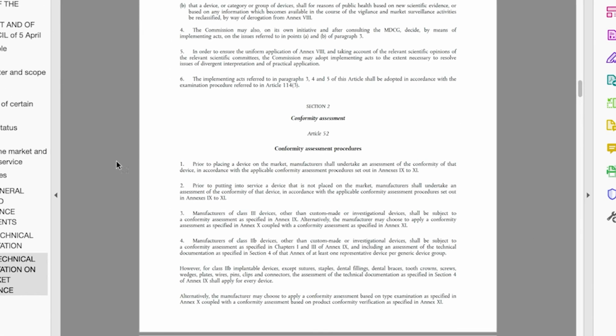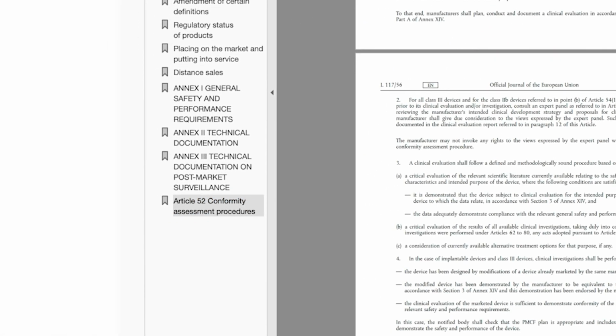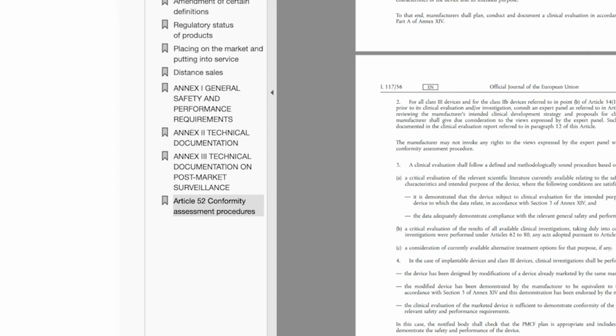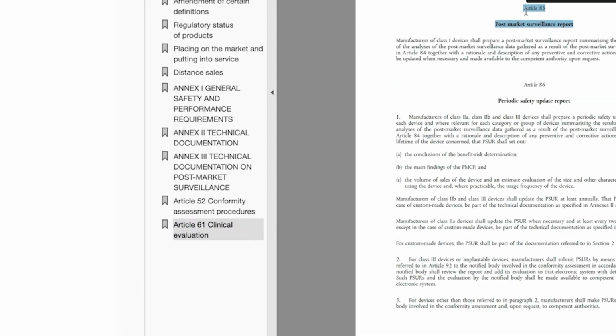Then start adding bookmarks for those articles you find interesting, such as, for example, Article 52, Conformity Assessment, Article 61, Clinical Evaluation, Article 84, Post-Market Surveillance, and so on. But don't forget the annexes. As I said, that's where the answers are. And if you are taking this course outside the EU, Articles 11 to 15 might be of utmost importance.